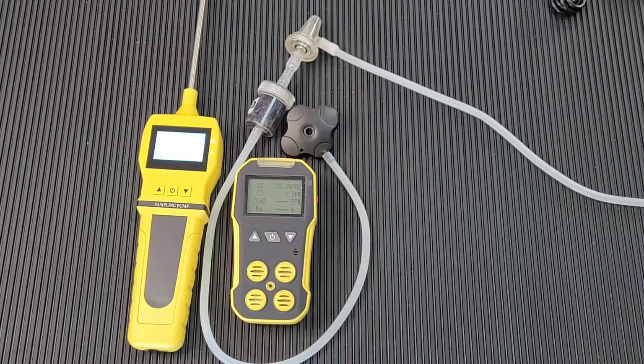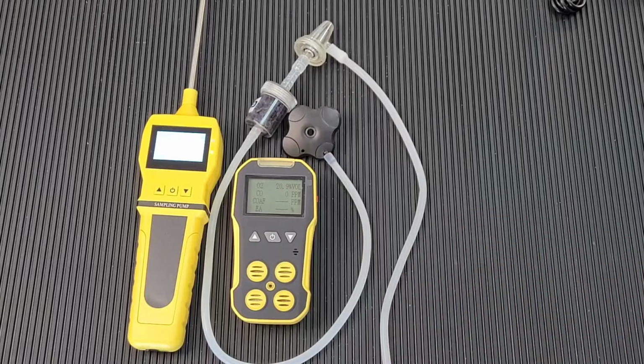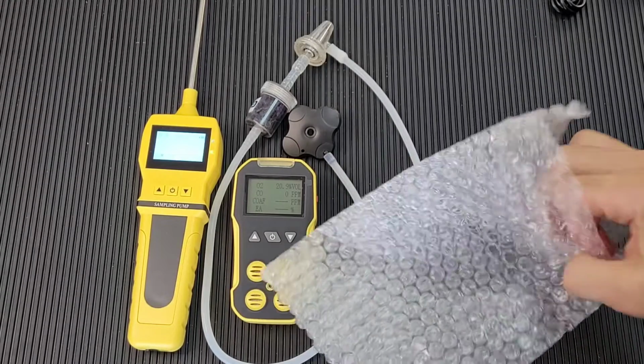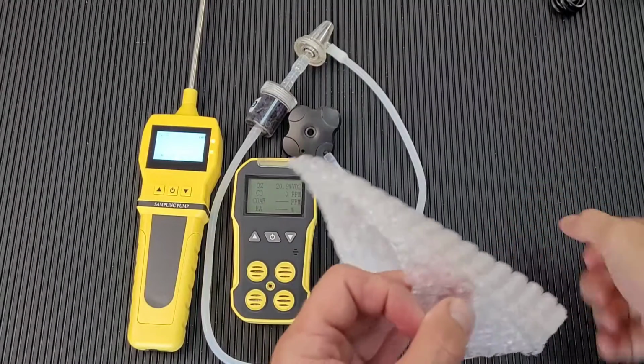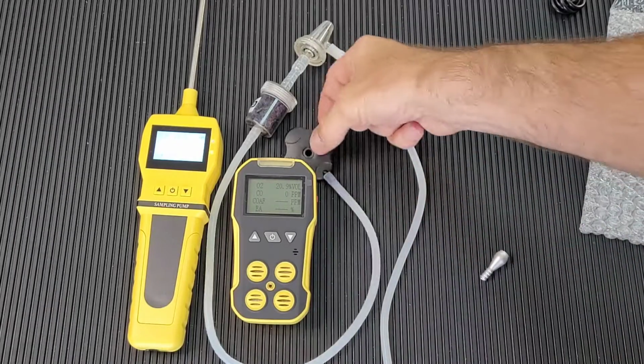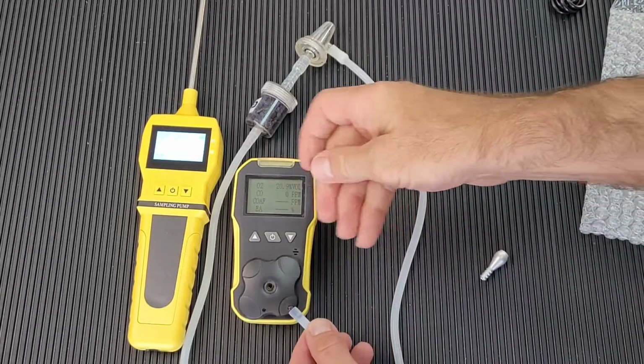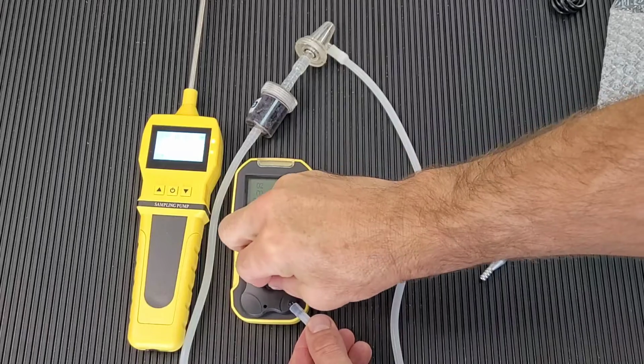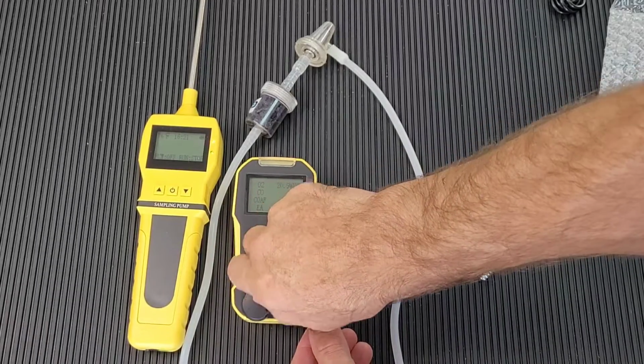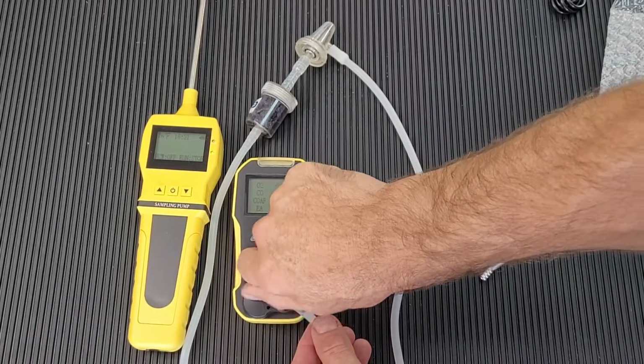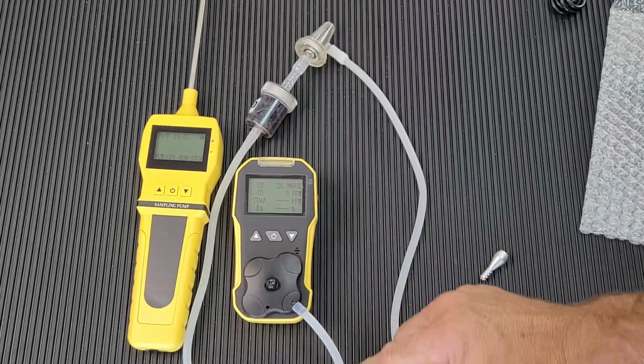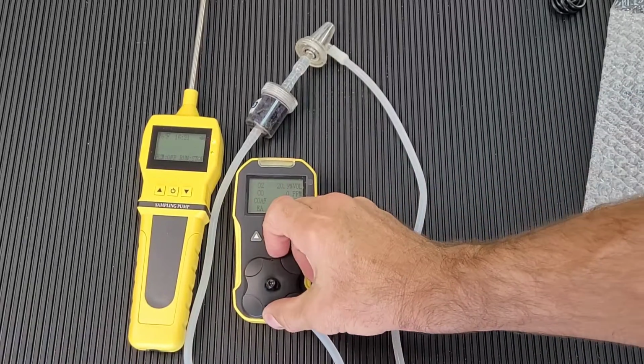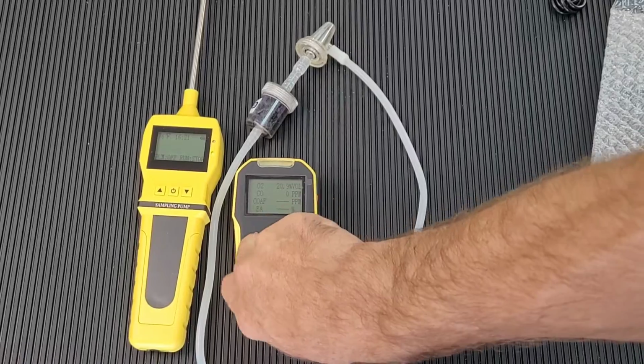Okay, I've unwound the tubing, and this is the basic setup, folks. Go to your bag, and in the bag you'll have two items. One is the screw, so grab the screw and grab the cap, and simply go ahead and screw on the calibration cap, that's what we call it, onto the detector, just like so. This allows the air to go to the sensors and to be analyzed. Okay, it's very important. Keep it nice and tight.